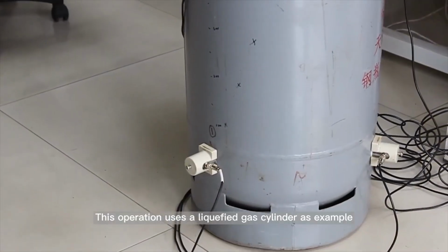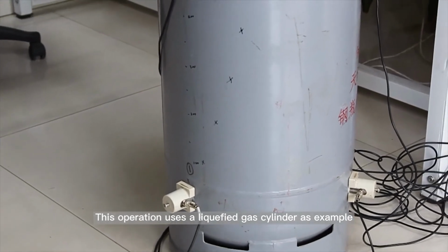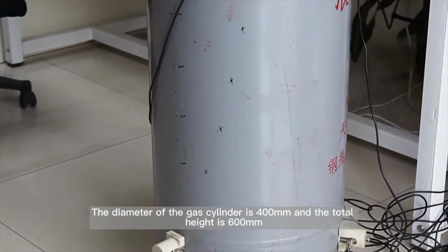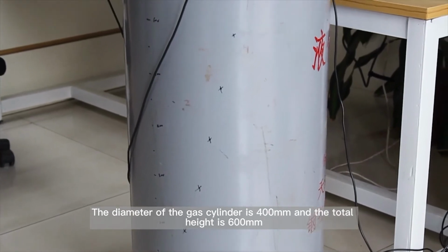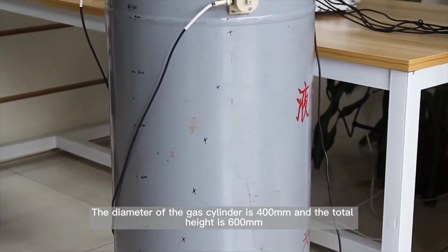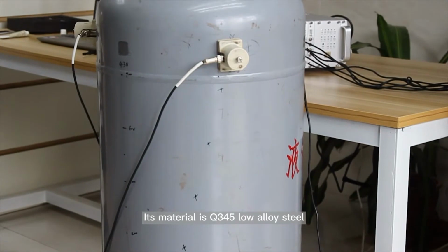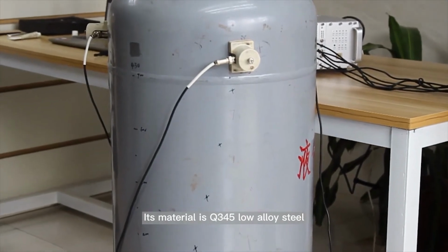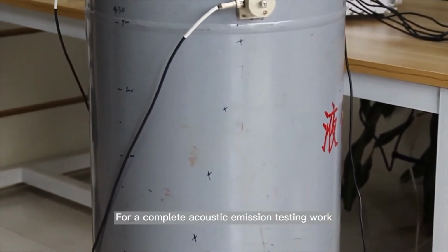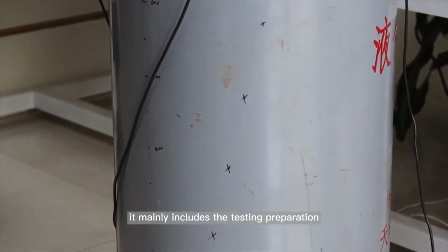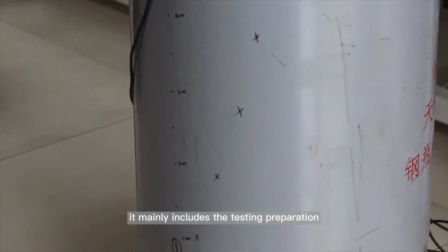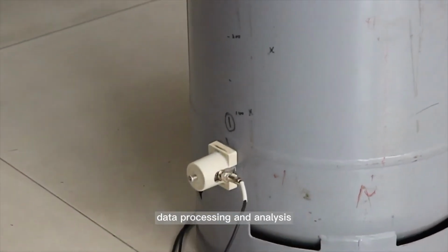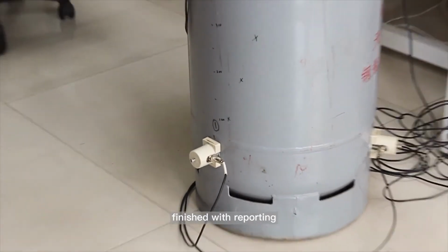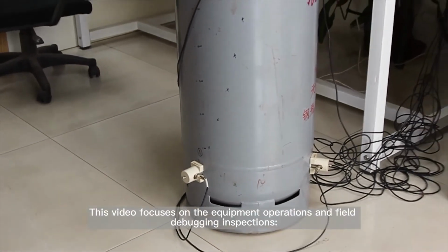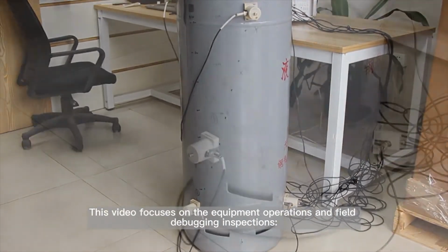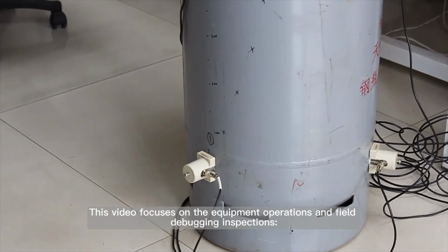This operation uses a liquefied gas cylinder as an example. The diameter of the gas cylinder is 400 mm and the total height is 600 mm. Its material is Q345 low alloy steel. For complete acoustic emission testing work, it mainly includes the testing preparation, on-site testing, data processing and analysis, finished with reporting. This video focuses on equipment operations and field debugging inspections.